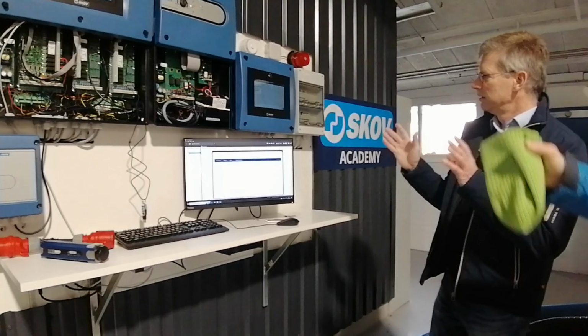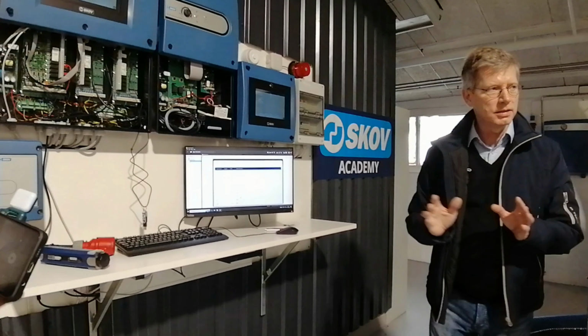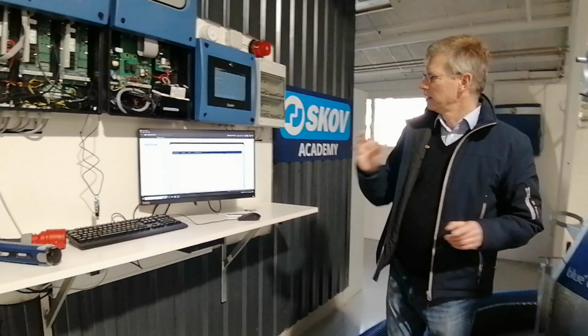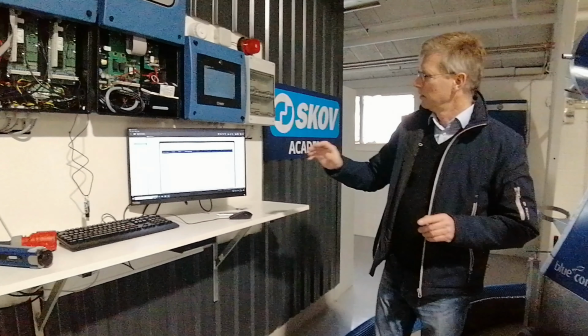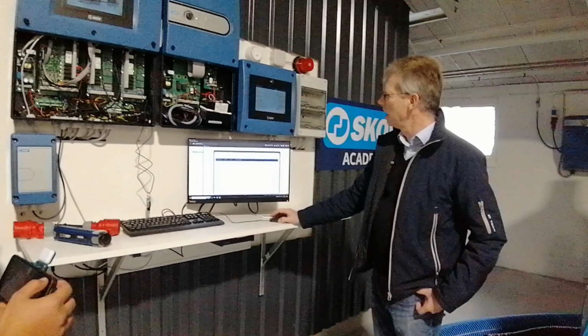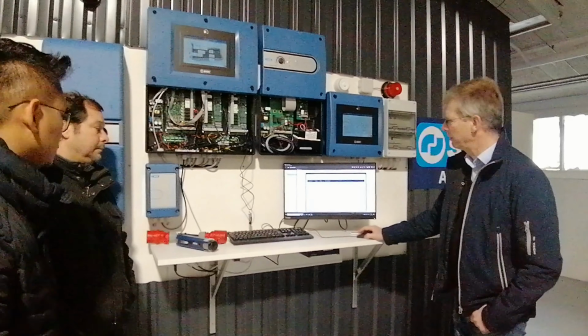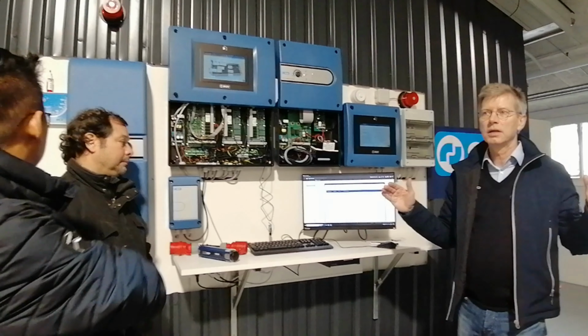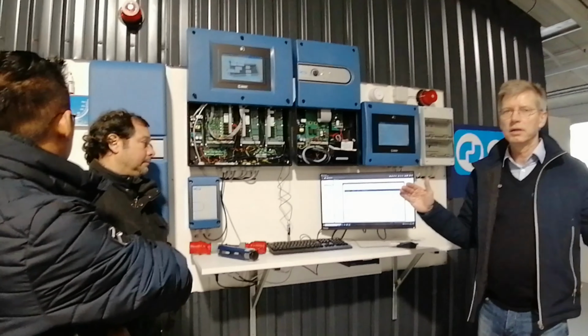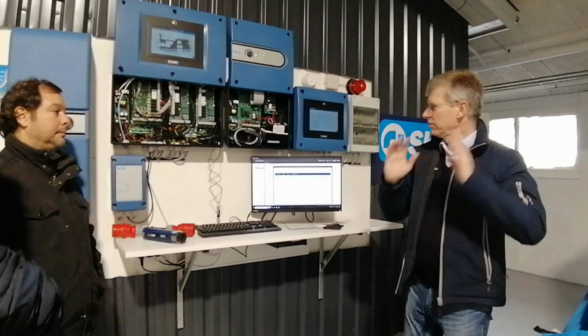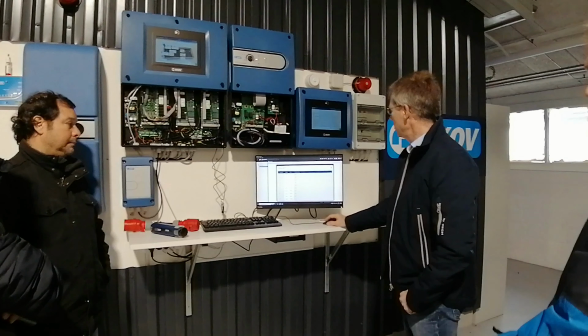No, to have a pressure - the idea is that we keep the inlet opening percentages as recommended by our service manual, and then we adjust the outlet capacity so that we get the right throw length of the air jet when it comes into the inlets. I'll demonstrate this, because now I'll go to curve point 6 or something.